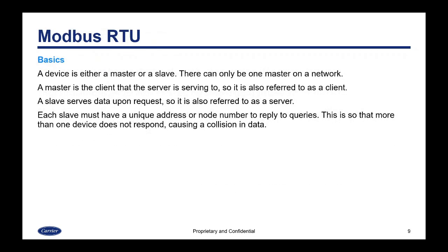With Modbus RTU, a device is either a master or a slave. There can only be one master on a network. A master is the client that the server is serving to, so it is also referred to as a client. A slave serves data upon request, so it is also referred to as a server. Each slave must have a unique address or node number to reply to queries, so that more than one device does not respond, which would cause a collision in data.